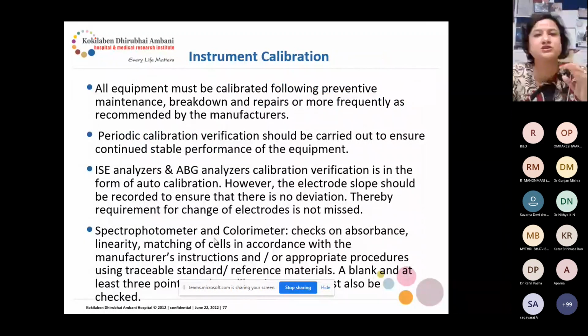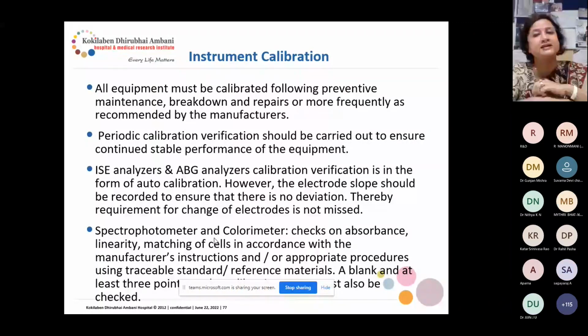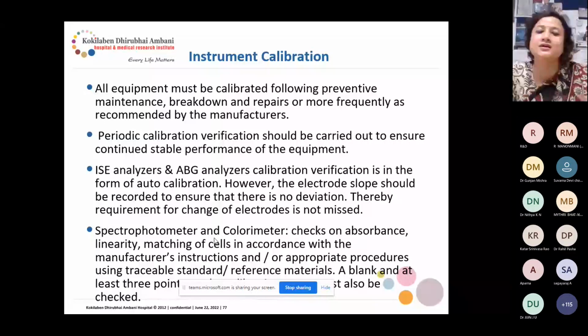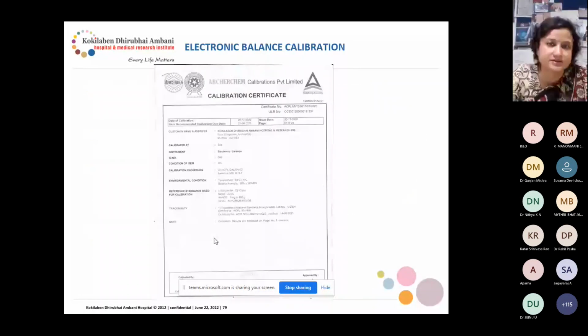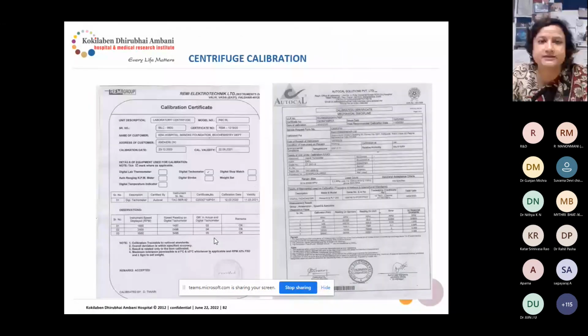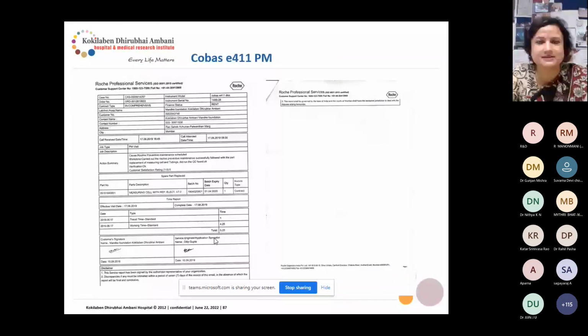Then coming to instrument calibrations, all equipment must be calibrated following preventive maintenance, breakdown and repairs, and more frequently as recommended by the manufacturer. We all know about calibrations, and many analyzers like ABG analyzers have auto calibrations. For the spectrophotometer and colorimeter, check absorbance, linearity, and matching of cells in accordance with the manufacturer's instructions or an appropriate procedure. I will show the calibration certificates of different instruments, such as the centrifuge. These are some examples of how a calibration certificate is given.